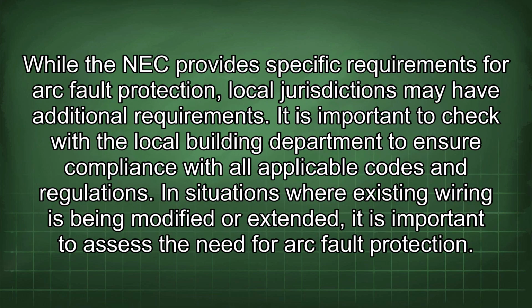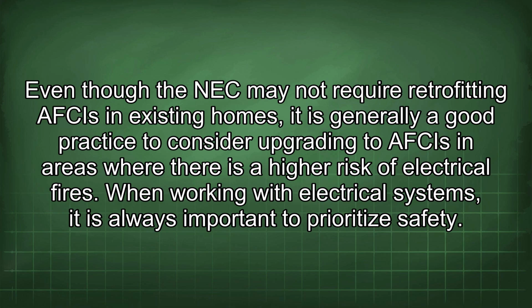Sometimes, it might be necessary to upgrade the AFCI to a more robust model that is less susceptible to nuisance tripping. While the NEC provides specific requirements for arc fault protection, local jurisdictions may have additional requirements. It is important to check with the local building department to ensure compliance with all applicable codes and regulations. In situations where existing wiring is being modified or extended, it is important to assess the need for arc fault protection. Even though the NEC may not require retrofitting AFCIs in existing homes, it is generally a good practice to consider upgrading to AFCIs in areas where there is a higher risk of electrical fires.